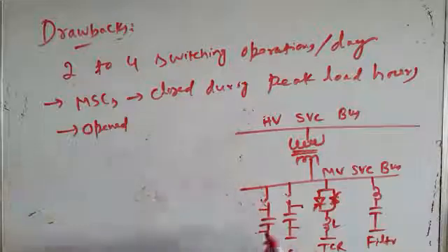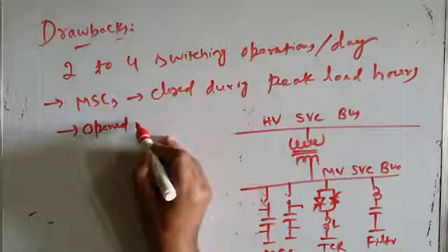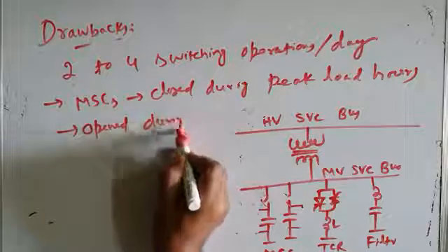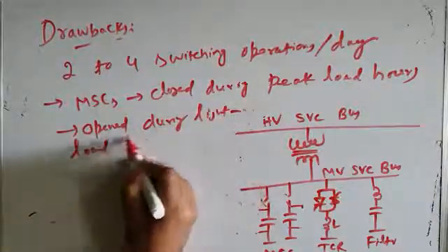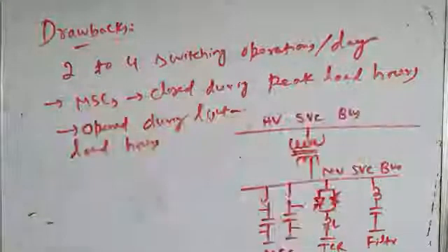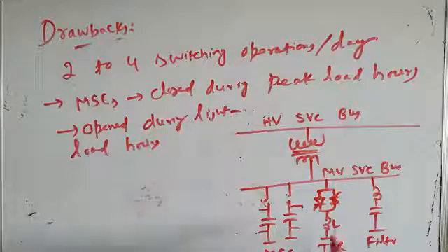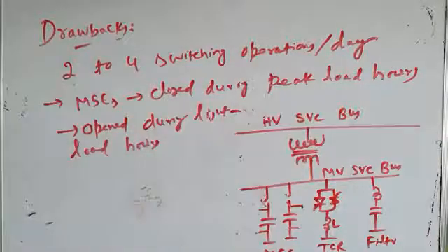So where only 2 to 4 switching operations per day are required, we prefer this MSC, TCR type SVC because the number of switching operations is very limited.